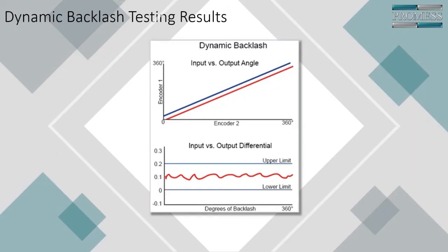And here's kind of a representative of that. And one additional point that I didn't really note here is one of the things we've learned over the years is we've created a differential graph based off this. So the first graph represents the counterclockwise graph and then the clockwise graph. And then we calculate a, so to speak, differential graph out of that. And then we can put upper and lower limits around that. Additionally, we can pull points off that graph anywhere we want to give you static measurements if you want, or go into more elaborate calculations for calculating averages, mins and max, and things like that.